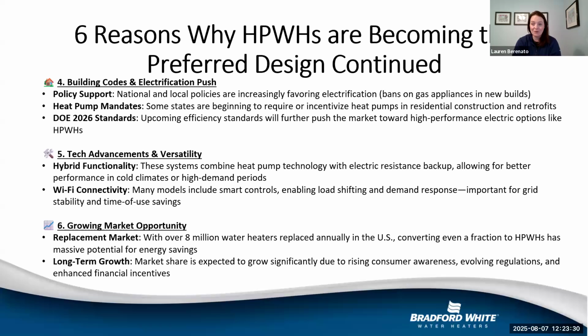We have a whole separate CEU on the DOE standards and changes that are going on. I was just finishing working on it because we're presenting it at the ASPE Tech Symposium in September. So really that's going to affect design mainly with retrofit. The majority of engineers and designers on today's call already are specifying the most thermally efficient methods for gas water heating. But it really comes down to, let's say you're in an older city like Boston or some parts of Montreal or Quebec City, and you are replacing an atmospheric water heater and you have to replace it with something that is not what was there, because it's no longer thermally efficient.